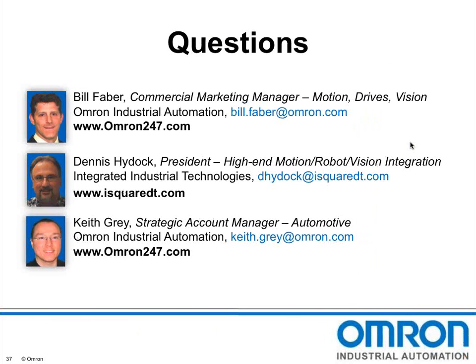In the Q&A session, David asked Bill whether EtherCAT is a universal protocol applicable to all automation-level equipment, or a proprietary network. Bill answered that EtherCAT is an open network — one of the reasons Omron selected it. It has the ability to do real-time control while also embedding non-real-time data frames to pass information. As Keith demonstrated, you can pull out and reinstall a servo drive, downloading parameters from the master and HMI without needing a PC — real-time and non-real-time data on the same network.